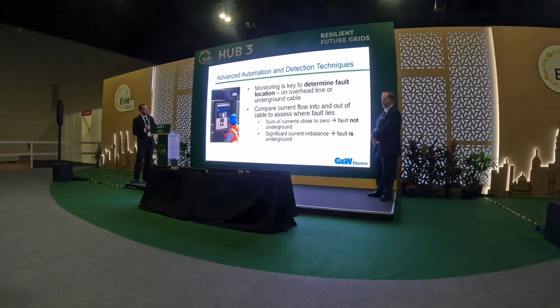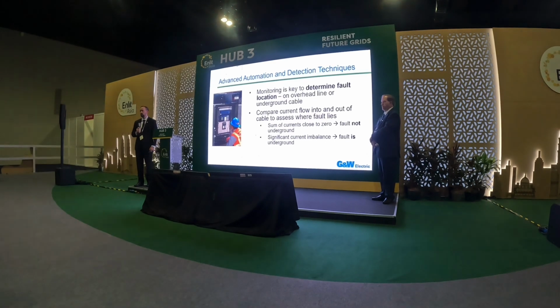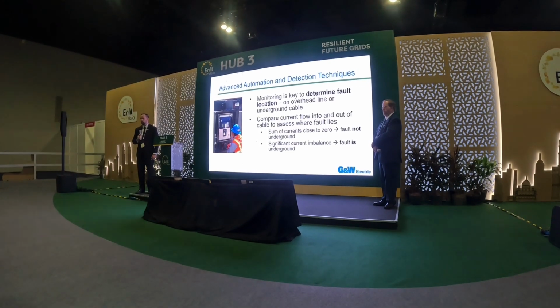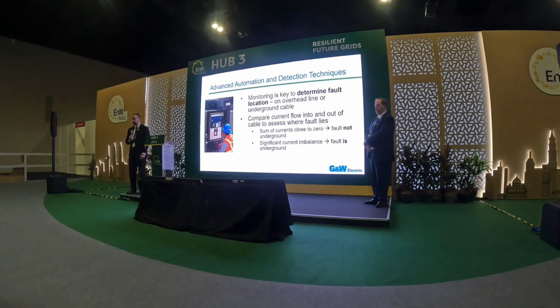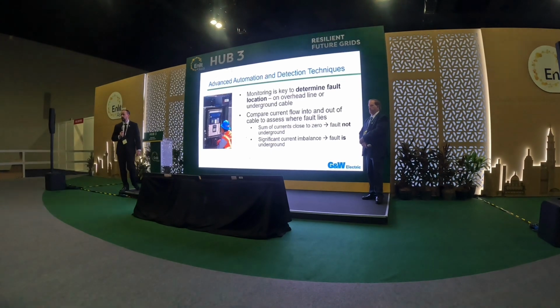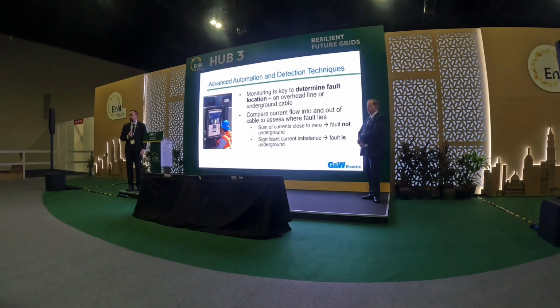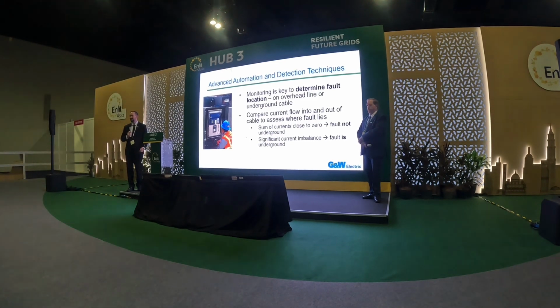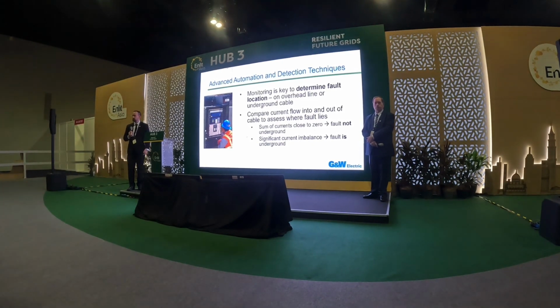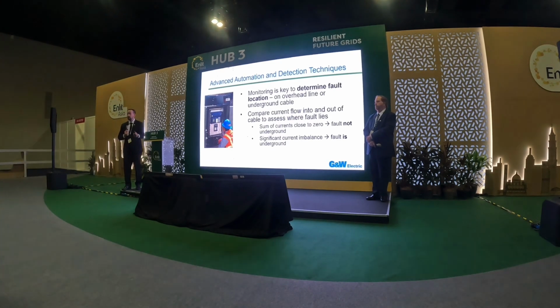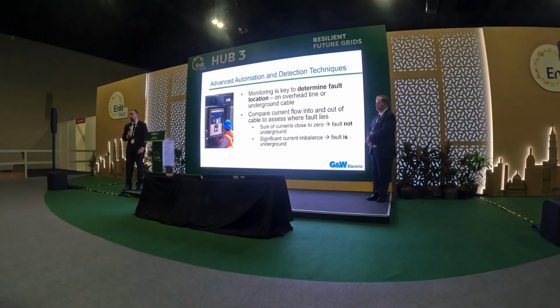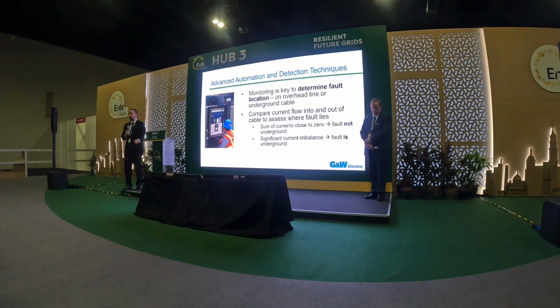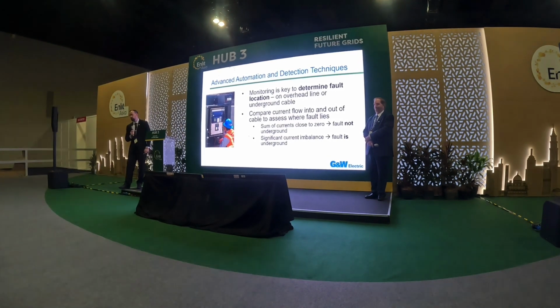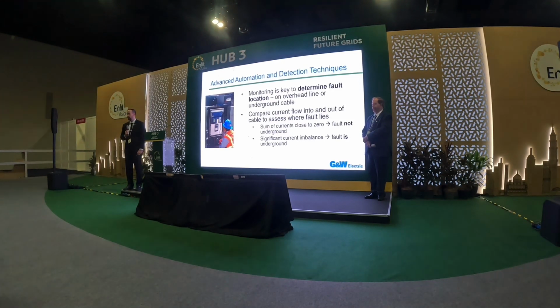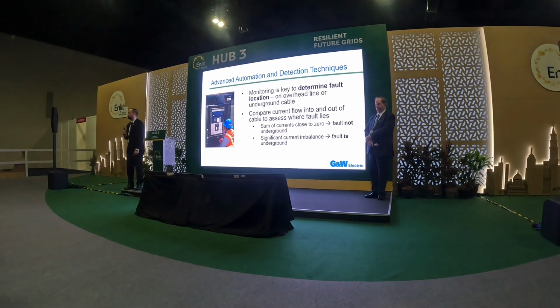What we ended up using for this application is a differential protection methodology. So Ron mentioned reclosers, right? Devices with integrated CTs on the line. This particular utility had a device like this at both transition points where the circuit was transitioning from overhead to underground, which gave them the ability to measure real-time current information at that transition point.